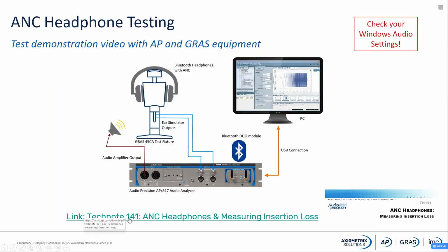I think the first thing to consider is that in order to be able to compare one device under test to another, we need to provide the same conditions for the test fixture. So we need to know that the measurement system of the DUT was measured within the same conditions.